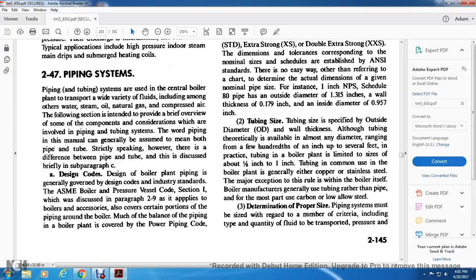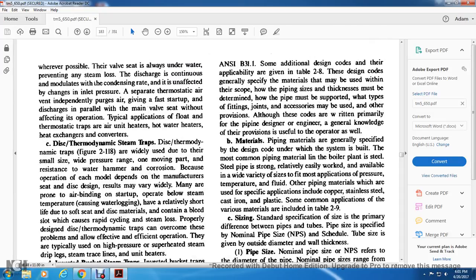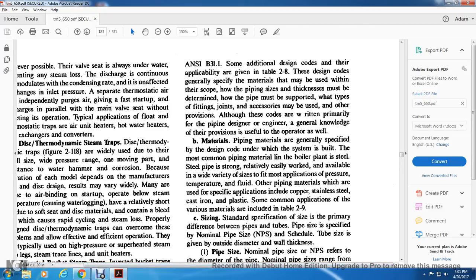Design codes. The design of boiler plant piping is generally governed by industry design codes and standards. The American Society of Mechanical Engineers Boiler and Pressure Vessel Code, Section 1, was discussed in paragraph 2.9, as it also applies to the boiler's accessories, covering a certain portion of the piping around the boiler. But much of the balance of the piping in the boiler plant is covered by a power piping code, American National Standards Institute B31.1. Additional design codes and their applicability are given in Table 2-8. The design code specifies the materials that may be used for its scope, how the pipe wall thickness must be determined, how the pipe must be supported, and the types of fittings, joints, and accessories that may be used. Other provisions apply as well. Although the codes are written primarily for the piping designer and engineer, general knowledge of the provisions is useful to the operator as well.